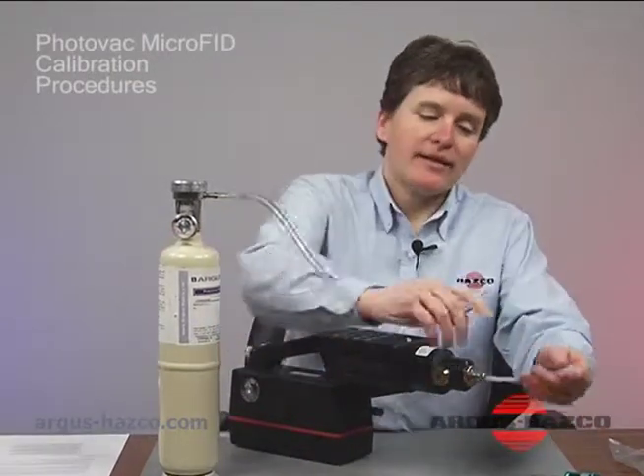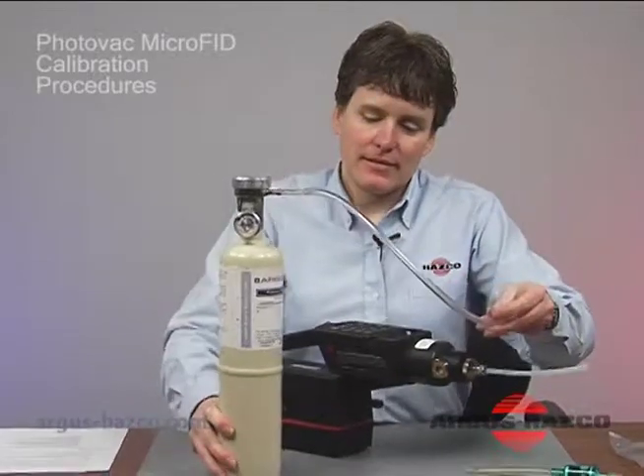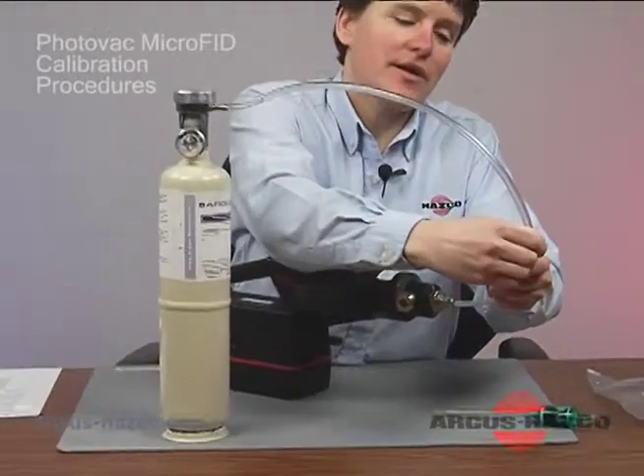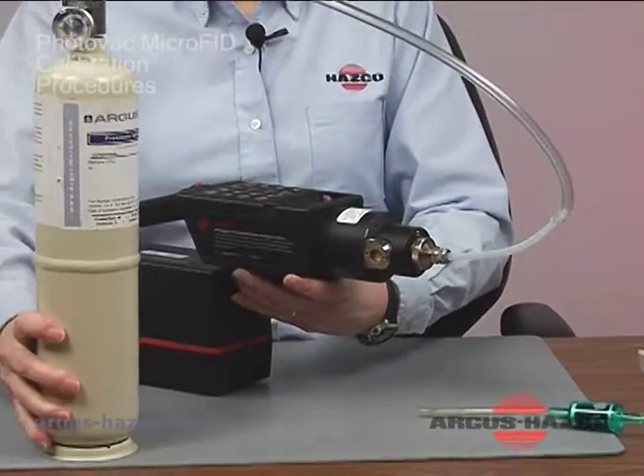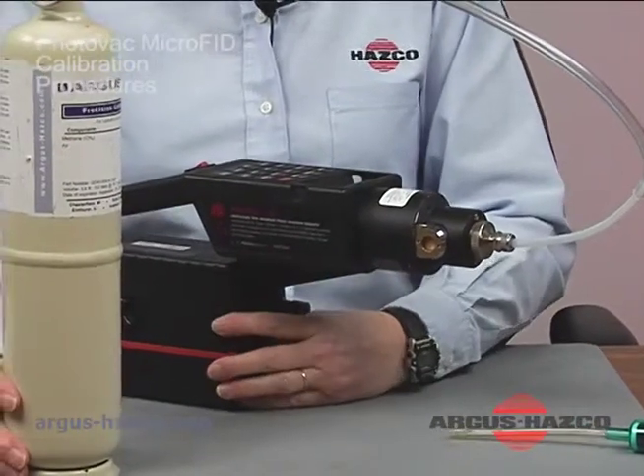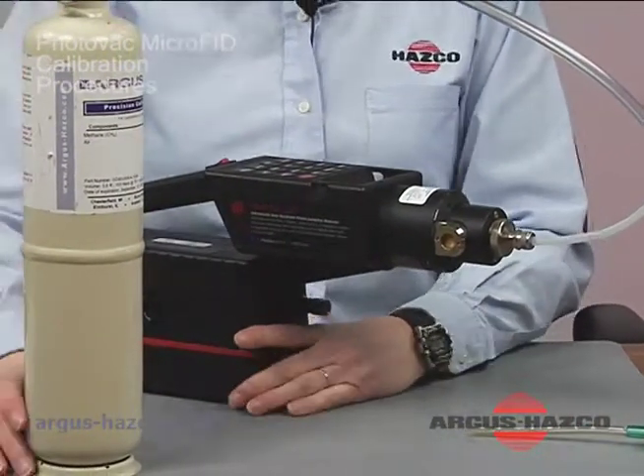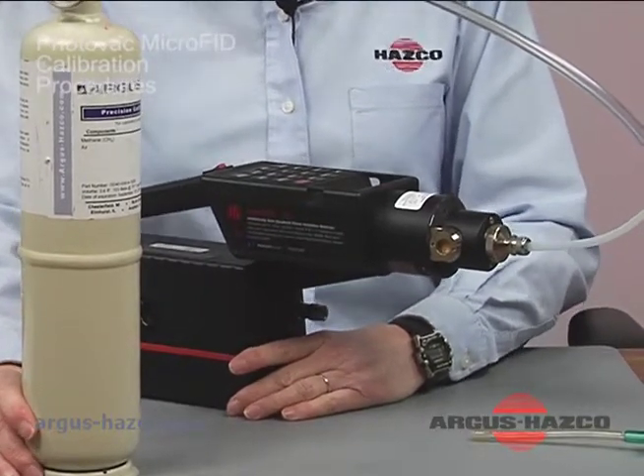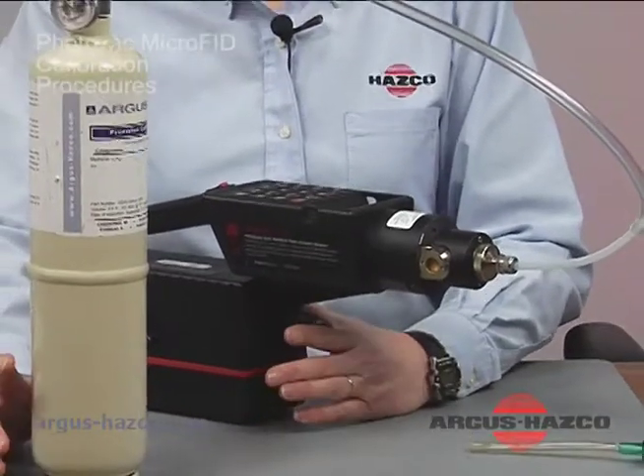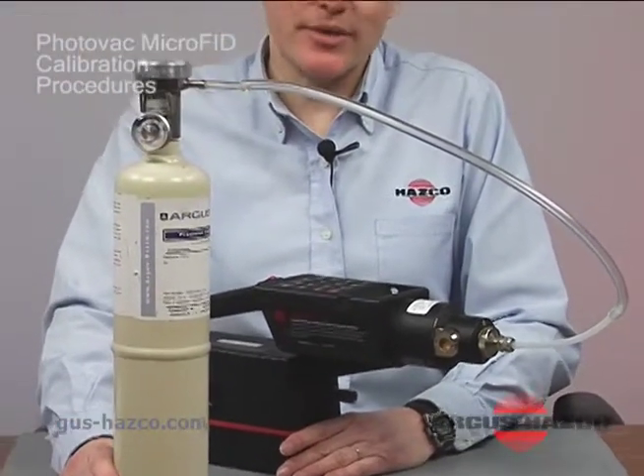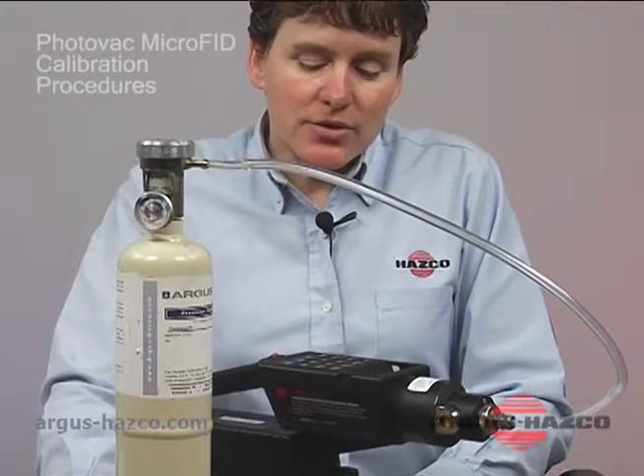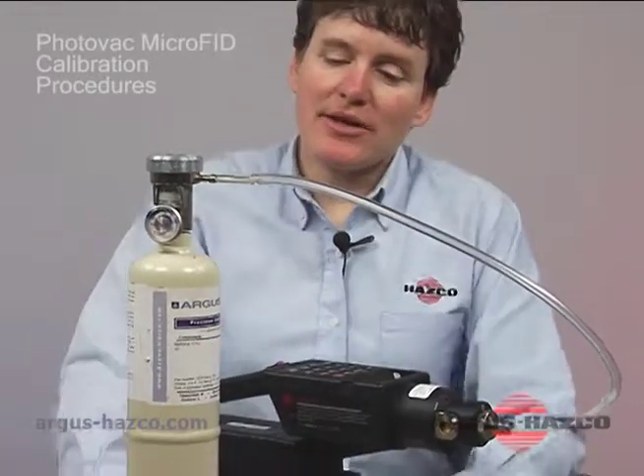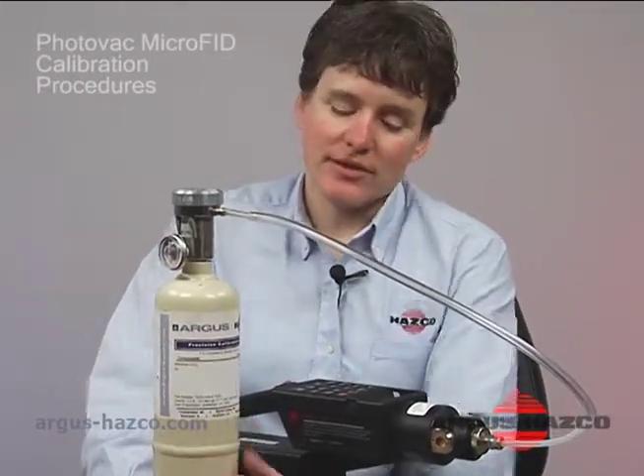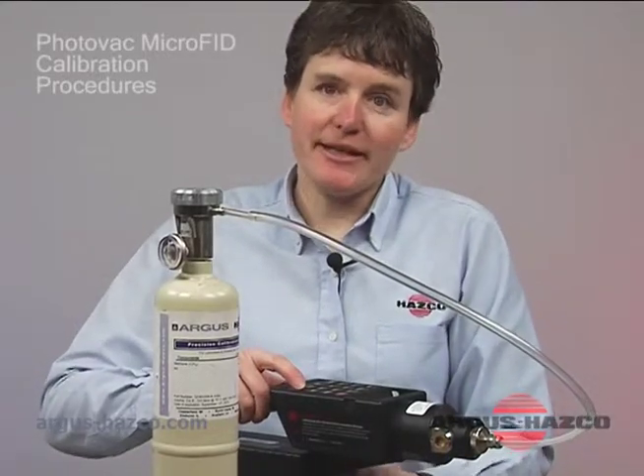And we want to go ahead and connect our tubing to our inlet probe. I like to let the pump pull off of the calibration gas cylinder for at least a minute before I hit my enter key. The manufacturer recommends that you have your flow of gas through the unit anywhere from 2 to 3 minutes to get a good stable reading. So my 100 ppm matches my 100 ppm on my cylinder. I'm going to go ahead and hit my enter key.